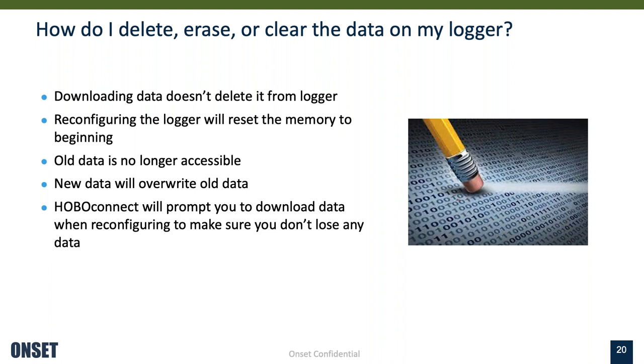The memory itself. Downloading that data from the logger will not delete the data from the memory. In fact, there's no real delete function in the typical data logger. However, when you reconfigure the logger, that goes back and tells the memory to start at zero and then overwrite all of the old data. So once you go through that reconfiguration process, that older data at that point is just no longer available. It's not accessible.